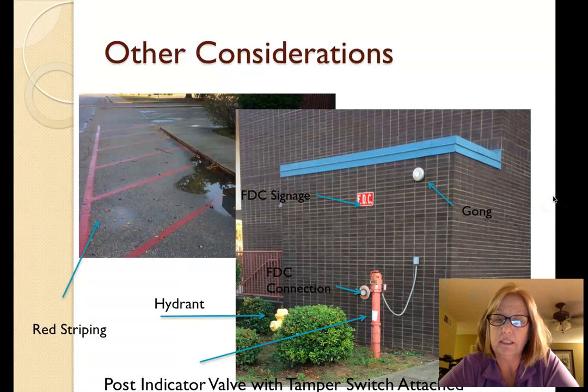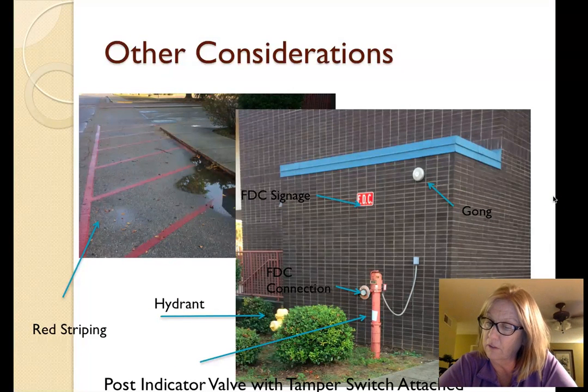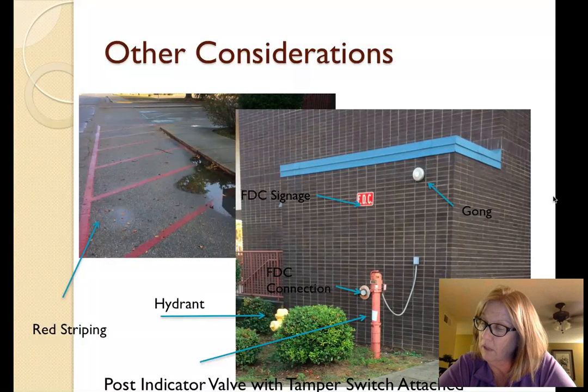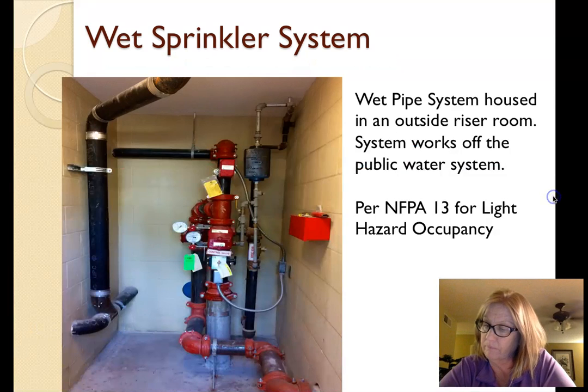The fire department connection, as you can see in this picture also, was correct. According to a light hazard occupancy, NFPA 13, it needs to be a twin 2.5-inch inlet fire department connection with cover plates. Red fire lane markings were also painted on the roadway next to the sprinkler room.